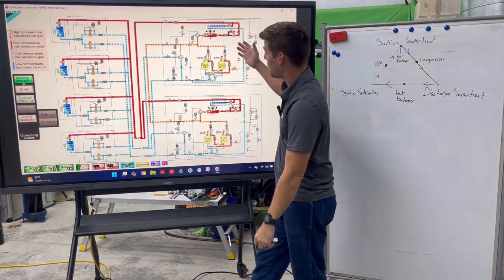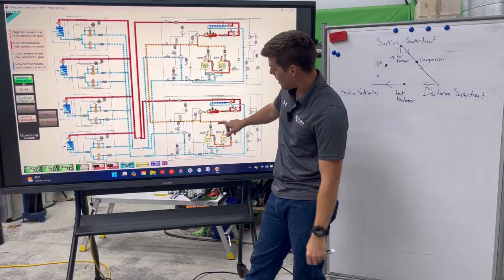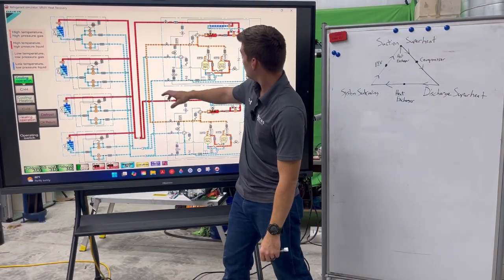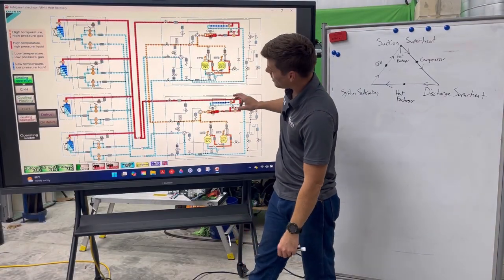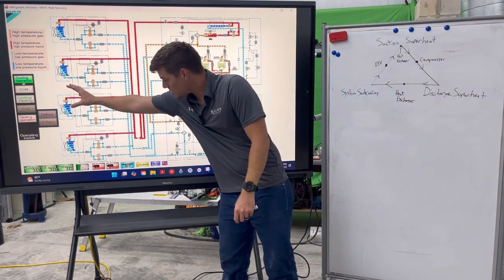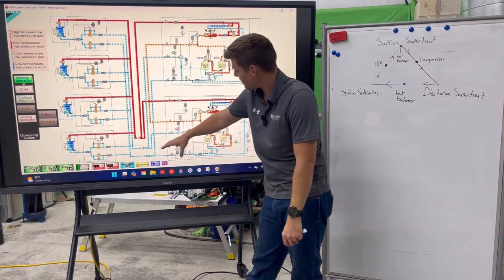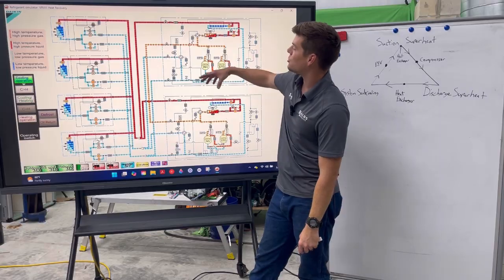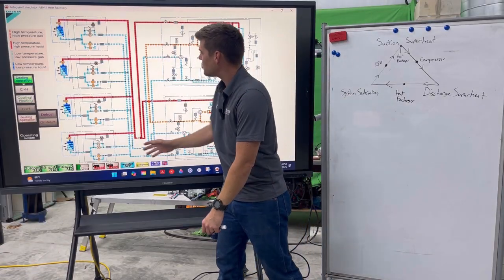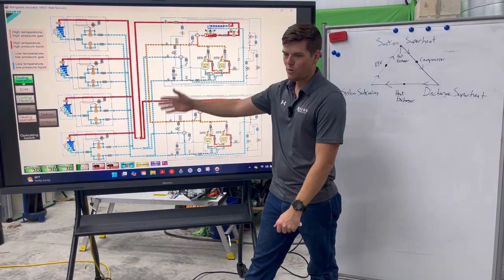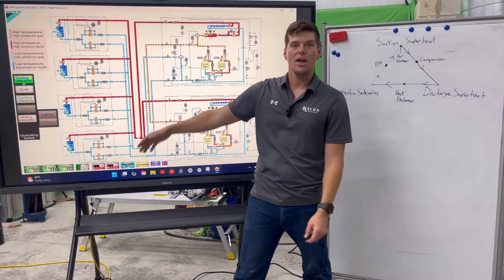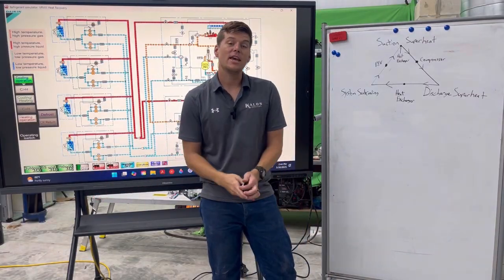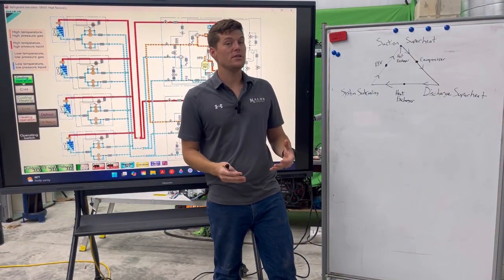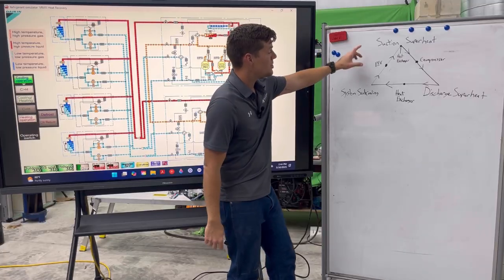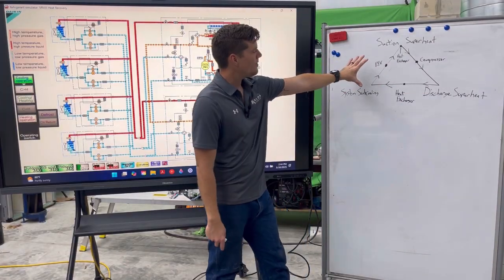And when you look at it here on this board, right, we leave the top of our compressors, we go out, we go through our heat exchangers, we come out as a liquid, that liquid goes to the indoor units, we get our suction superheat as we come back, and we go back to our compressors, and then discharge superheat, system subcooling, and so on, back and forth, and it never ends. Again, when we talk about troubleshooting VRF systems, you have to understand the connection between all 3 of these and where they fit into the system.